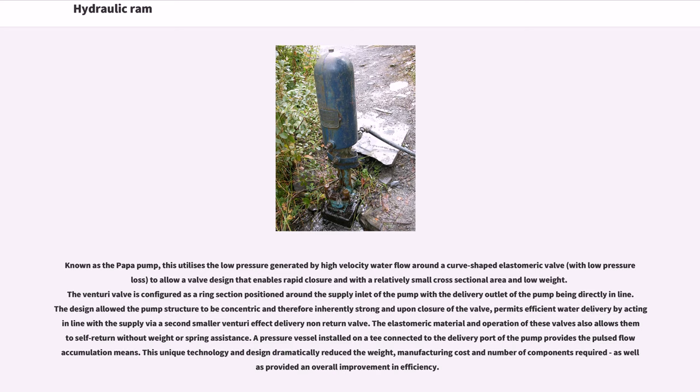Known as the Papa pump, this utilizes the low pressure generated by high velocity water flow around a curve-shaped elastomeric valve, with low pressure loss, to allow a valve design that enables rapid closure with a relatively small cross-sectional area and low weight. The venturi valve is configured as a ring section positioned around the supply inlet of the pump, with the delivery outlet directly in line. The design allowed the pump structure to be concentric and therefore inherently strong.